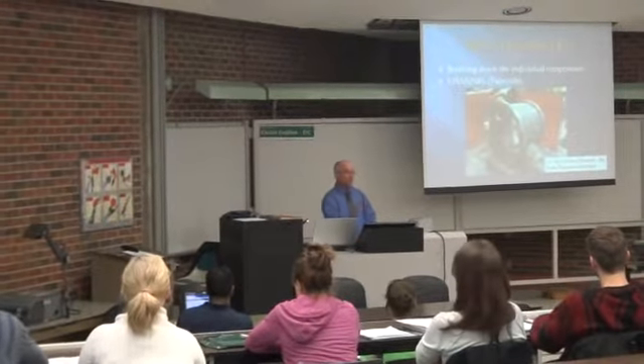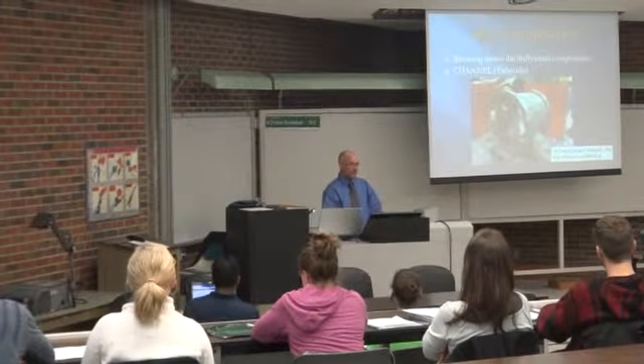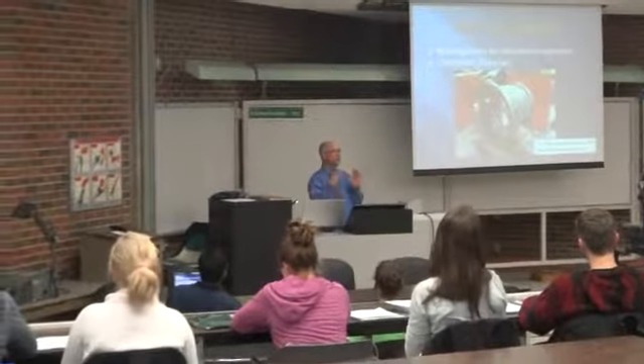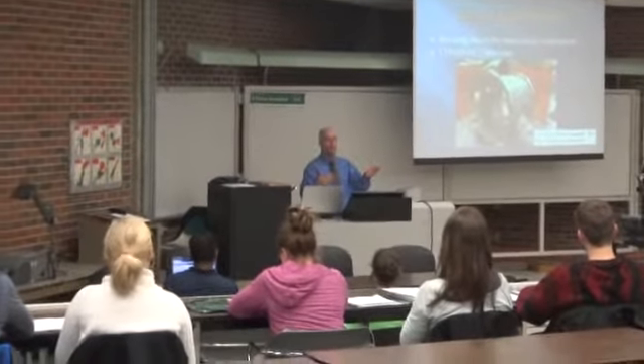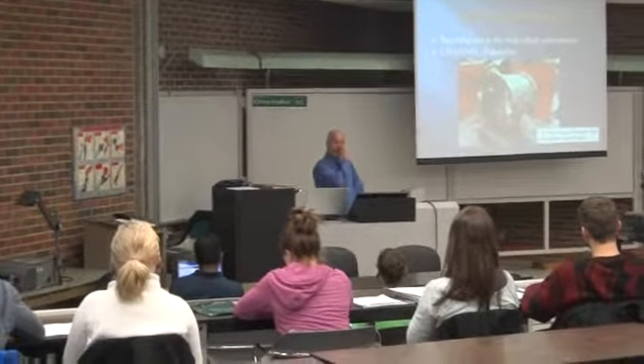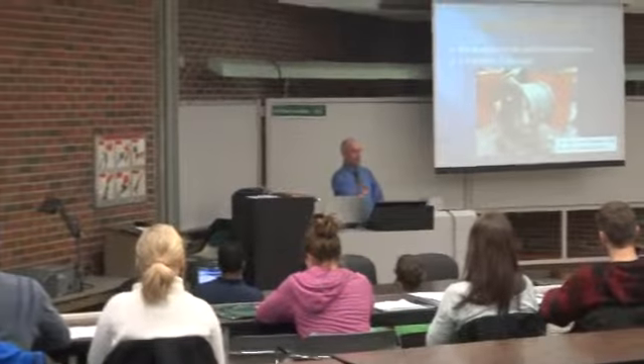So breaking it into components now. The very first one is the one I was referring to as the channel. That's the A component in the last slide. This is how it looks in our shop. So this is a piece of plate that's got two flanges on it. It's got two nozzles. And then we will put a divider plate in there, so that way it will have a pass plate, it's called. And the fluid will come in one nozzle, go down the bundle, come back out, and exit.